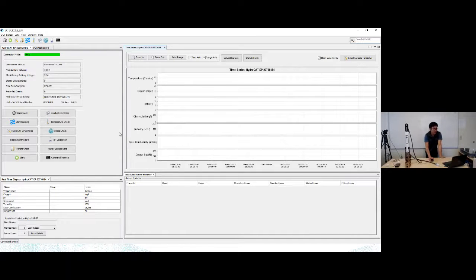Now, we don't have time to do the full pH calibration process here. I'll talk about it when we're doing the cleaning process. It's very similar, but again, 90-day calibration stability for this pH sensor. So this is where you would do it. You would click on the pH calibration button here. This window would pop up. Eventually, it might be elsewhere on my computer. And basically, it's going to walk you through the process of calibrating your pH sensor with pH 4, pH 7, and pH 10 buffer solution. It's a pretty straightforward process.